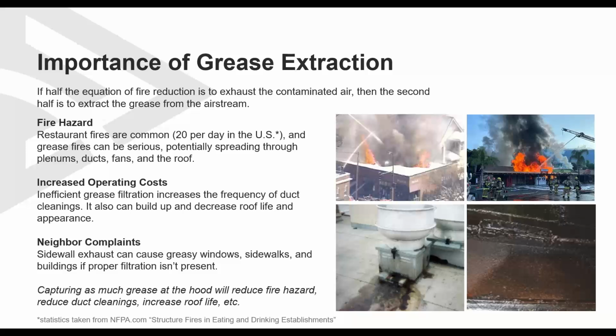So you may be asking, why is grease extraction so important? If half of the equation of fire reduction is to exhaust the contaminated air out, then the second half is to extract the grease from the airstream. Restaurant fires are very common, and grease fires can be very serious, potentially spreading through plenums, ductwork, fans, and up to the roof.